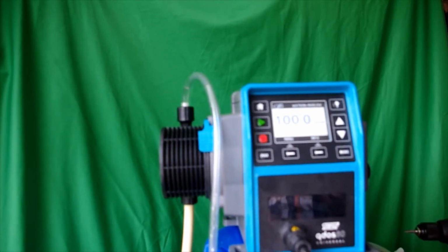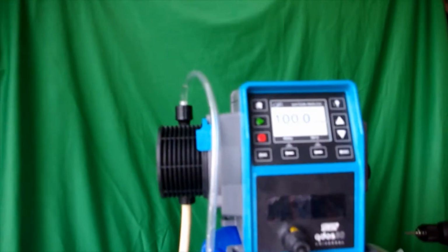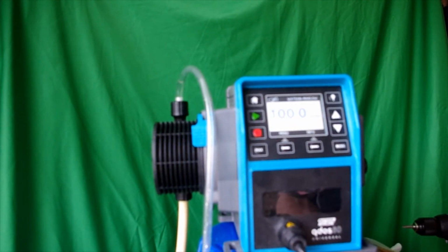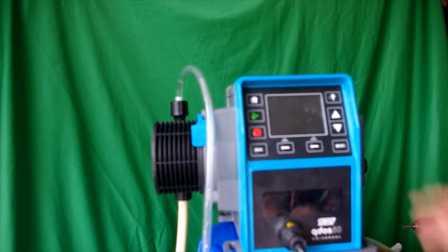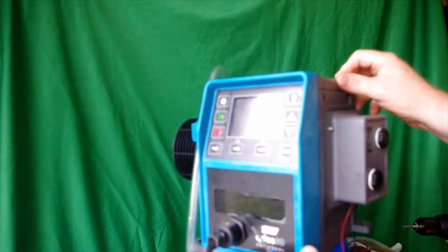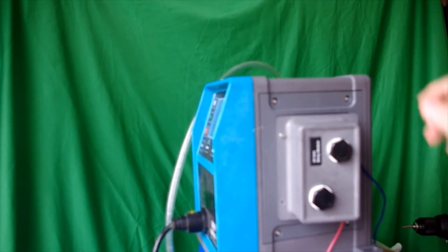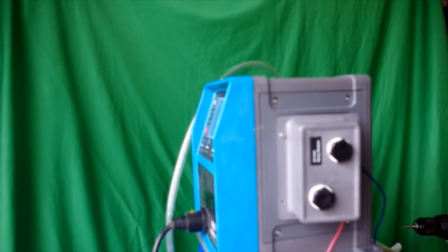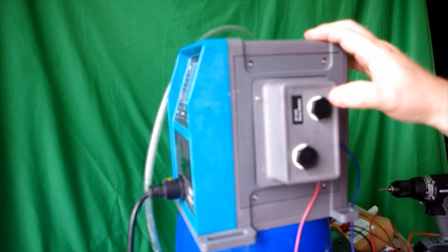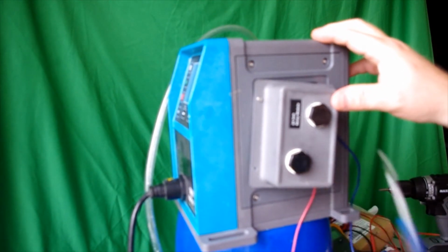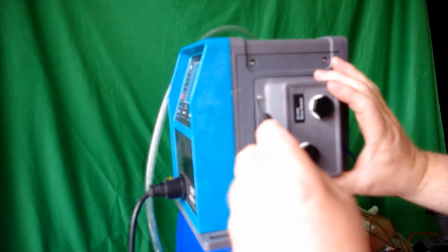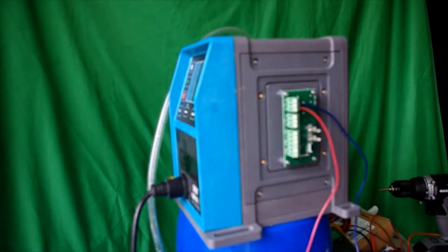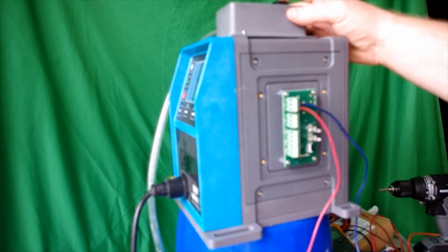You would unplug the mains lead power of the pump. And then you would get your pump in a working condition. In this case here, I think you can see, this is our NEMA module. This is a 24 volt alarm, as you can see here. And so you would have to take out this if you wanted to wire your alarm. There's 4 screws. For demonstration purposes, I've removed 3 of the screws already.